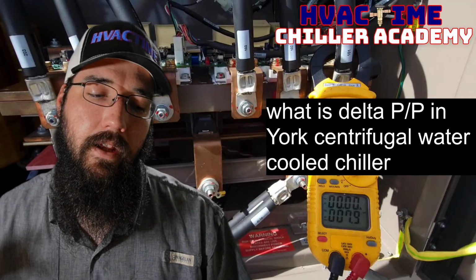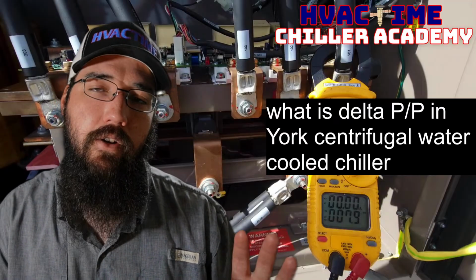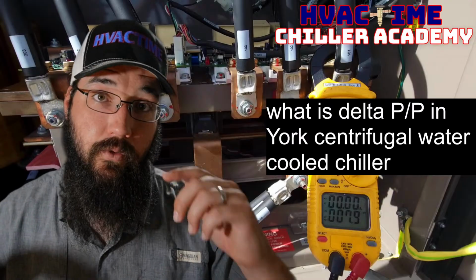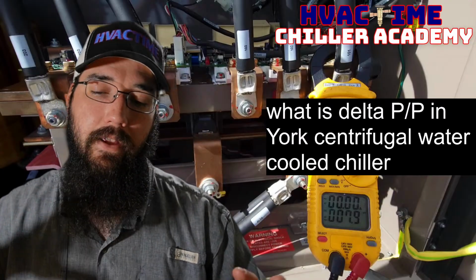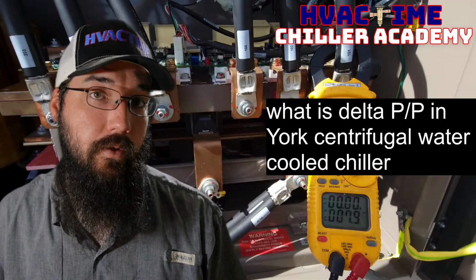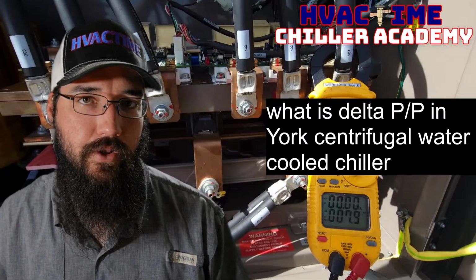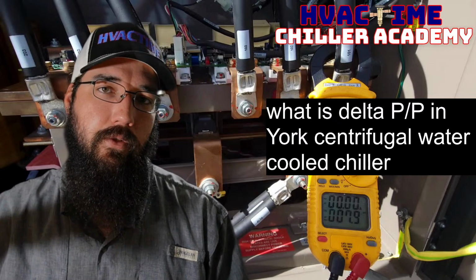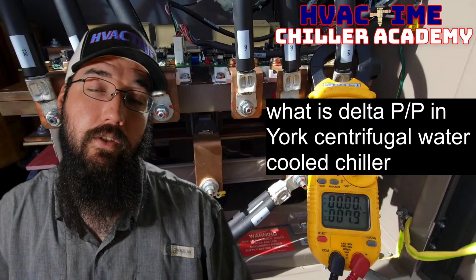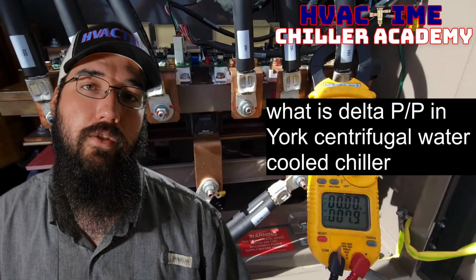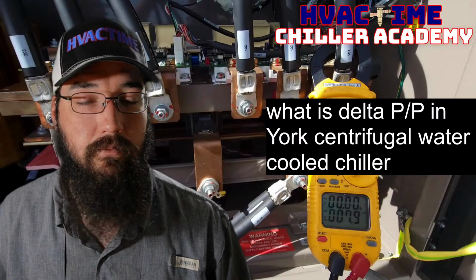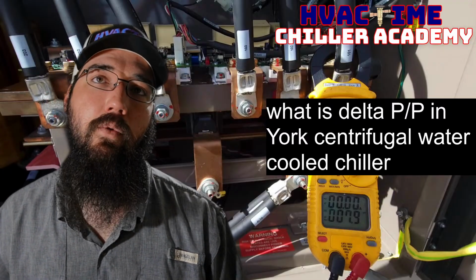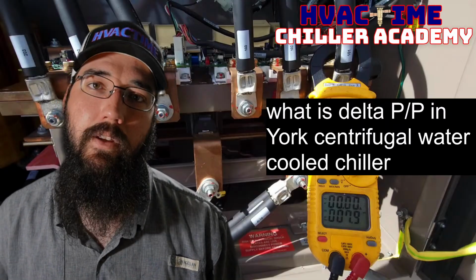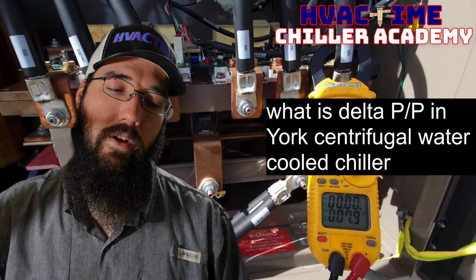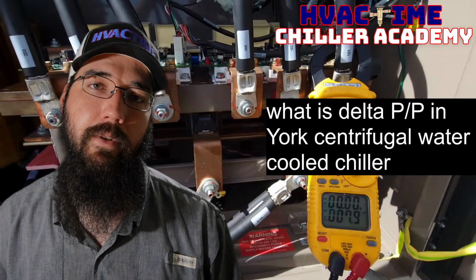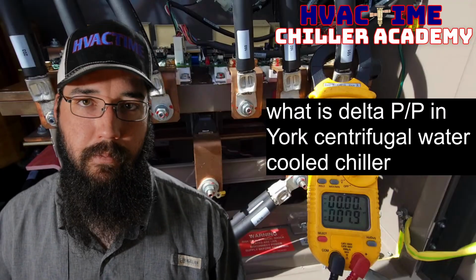And then it can avoid those, and it will allow it to go back into its normal, because part of what happens in that case is the machine can't unload effectively and run as efficient as it needs to. So that compressor will stay ramped up at high speed even though you may have a lower load, and then you can start pushing into cycling shutdowns, which is not a good thing, right? We don't want the chiller to shut down any more than it absolutely has to. So if we're shutting down on leaving water temperature because we can't unload the compressor, that becomes a problem.